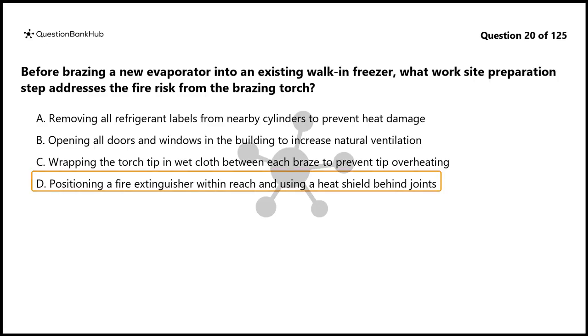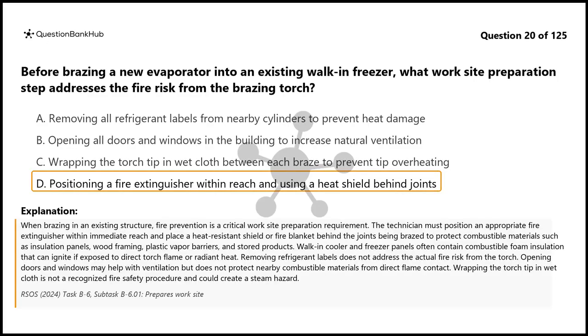The correct answer is D. When brazing in an existing structure, fire prevention is a critical work site preparation requirement. The technician must position an appropriate fire extinguisher within immediate reach and place a heat-resistant shield or fire blanket behind the joints being brazed to protect combustible materials such as insulation panels, wood framing, plastic vapor barriers, and stored products.